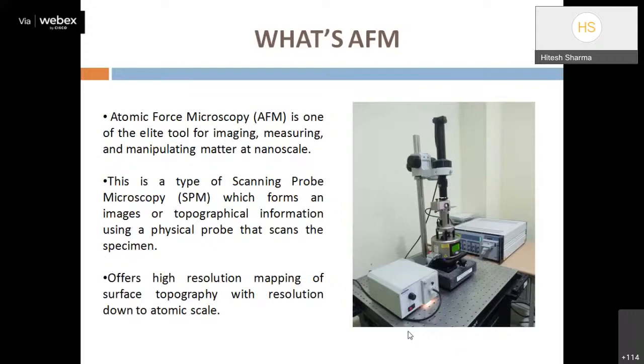The relative cost of the AFM imaging system is very low compared to SEM and TEM. SEM has medium relative cost while TEM has very high cost compared to AFM. Another advantage is the sample environment: AFM requires no vacuum environment, whereas SEM and TEM require vacuum, and TEM requires very high vacuum. Some environmental artifacts are present in AFM but they do not significantly affect sample information.